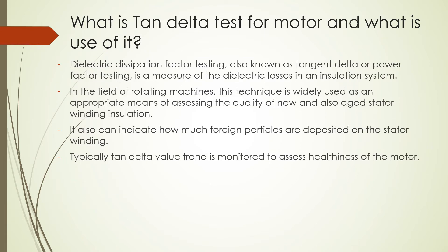The fifth question: what is the tan delta test for a motor and what is its use? Dielectric dissipation factor testing, also known as tangent delta or power factor testing, is a measure of dielectric losses in an insulation system. In the field of rotating machines, this technique is widely used to assess the quality of new and aged stator winding insulation. It can also indicate how much foreign particles have deposited on the stator winding. Typically, the tan delta value trend is monitored to assess the healthiness of the motor.